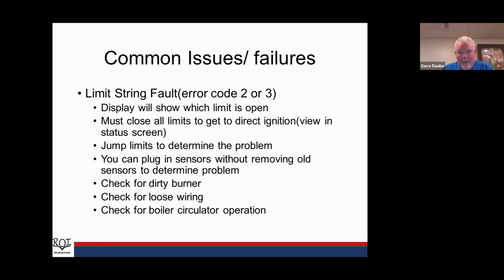Another thing we run into would be a limit string fault, and that's going to give you an error code 2 or 3 on the display. You can look at the display and it will actually show you which limit is open. It has a little blinking box. The first one that's blinking is your problem, so you need to get that taken care of. We have to close all of our limits in order to get to direct ignition, where the boiler actually lights. And if we just go to the status screen, we can see what part of the ignition process the boiler is in: pre-purge, drive light off, pre-ignition, and then it'll go to direct ignition. If we don't get to direct ignition, we've got a limit that's holding us up.